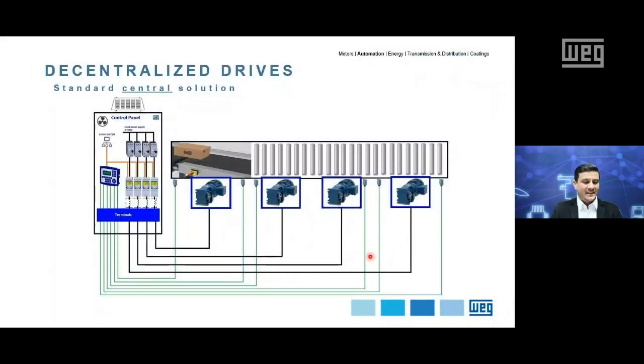So here we have a classical central solution concept. As you can see, the inverters are assembled inside the control panel, which means they are located far away from the motor. Therefore, in this case, we have a long cable distance between the VSD and the motor. And as already mentioned, depending on the cable distance between the VSD and the motor, an output filter may be required in order to avoid these voltage peaks which are delivered to the motor. So these filters can increase, of course, the total cost of the solution and make the control panel bigger.